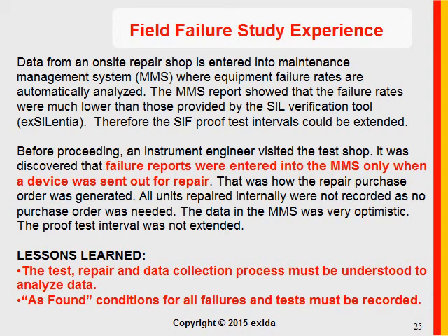In another incident, we discovered that data from an on-site repair shop in an end-user facility is entered into a maintenance management system where equipment failure rates are automatically analyzed. The MMS report showed the failure rates of some instruments being used in a safety function were much lower than those used for SIL verification in the exSILentia tool. Therefore, they concluded they could extend proof test intervals without sacrificing their necessary risk reduction.